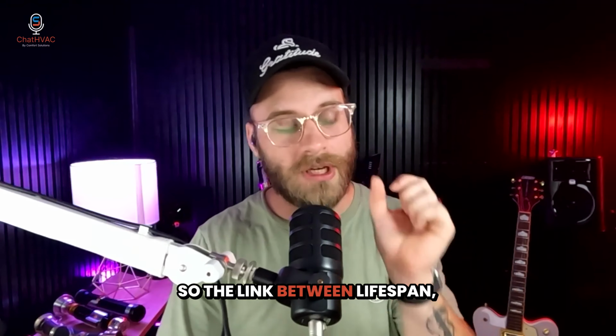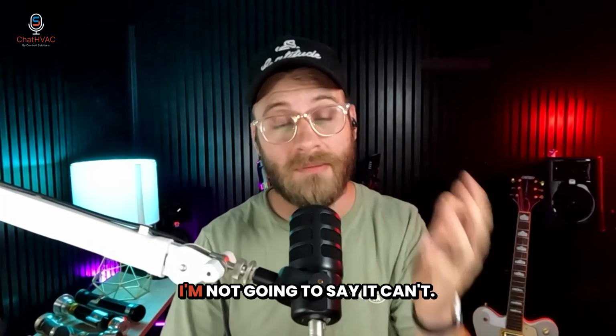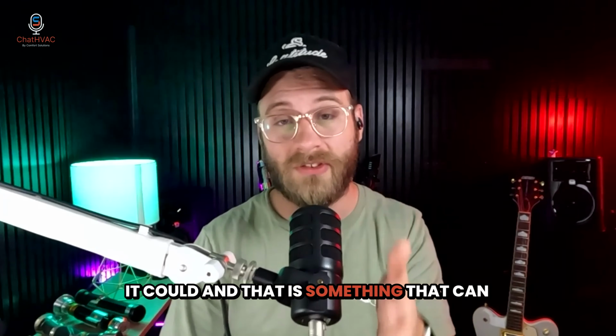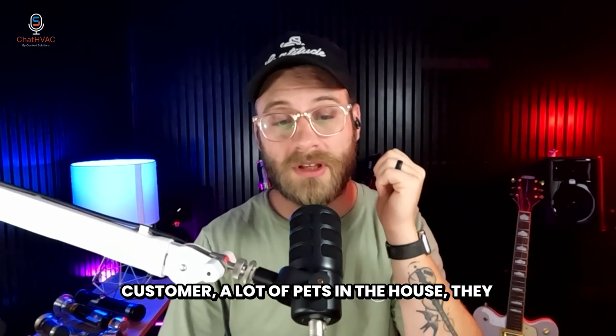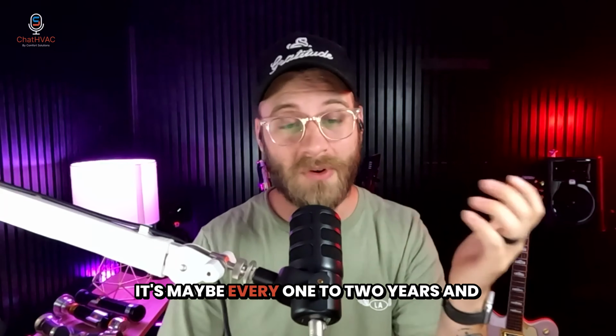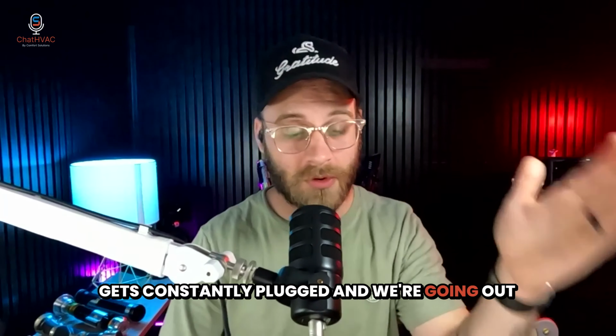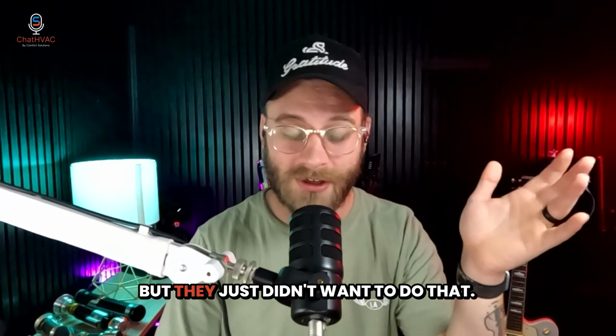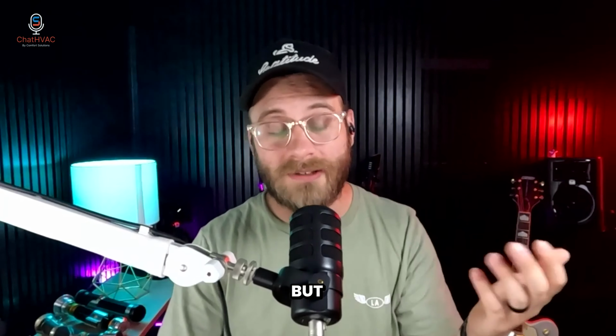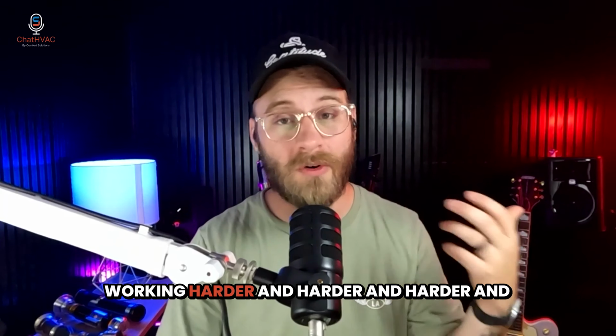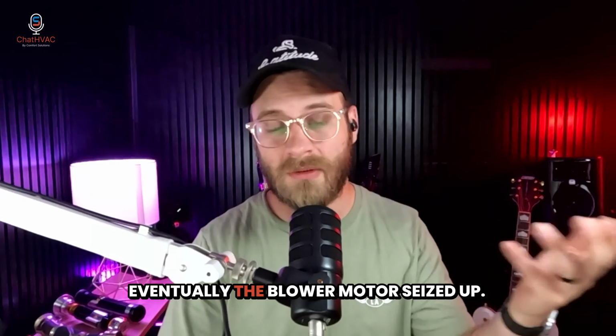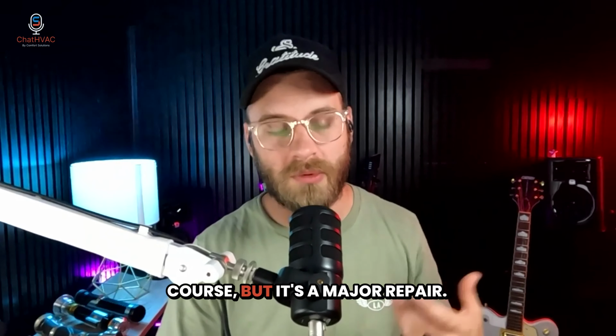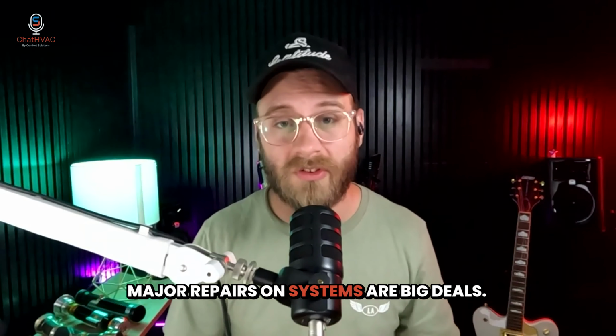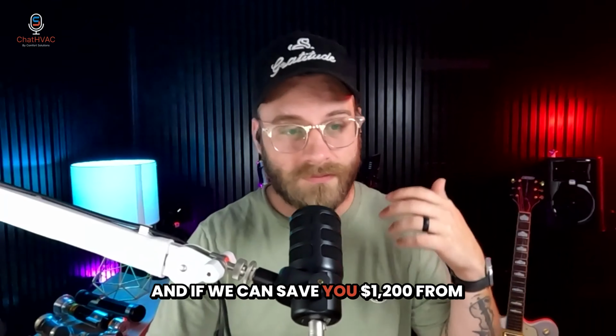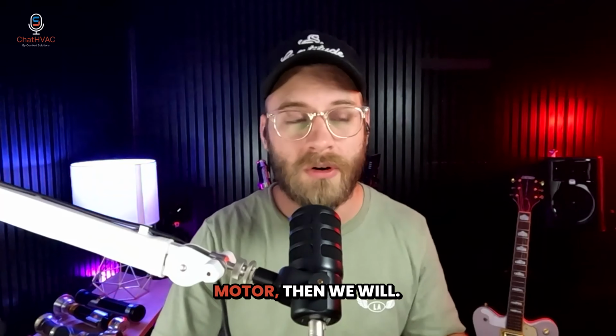So the link between lifespan and filters, is a filter going to 100% kill your system? I'm not going to say it can't. It could, and that is something that can happen. It's something I have seen happen where a customer with a lot of pets in the house didn't replace the filter regularly, maybe every 1 to 2 years, with a little 1-inch filter that gets constantly plugged, and we're going out for service calls all the time. We recommended a maintenance plan so we could change the filters for them, but they didn't want that. Over time the blower motor worked harder and harder, got dirtier and dirtier, and eventually the blower motor seized up. They didn't end up replacing the system, but it's a major repair, and major repairs on systems are big deals. If we can save you $1,200 from replacing a variable speed ECM blower motor, then we will.